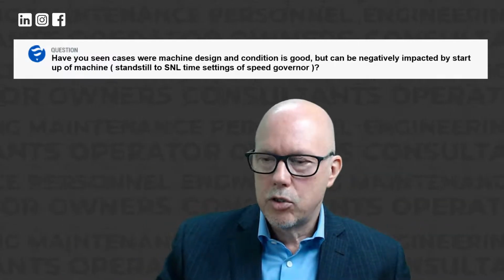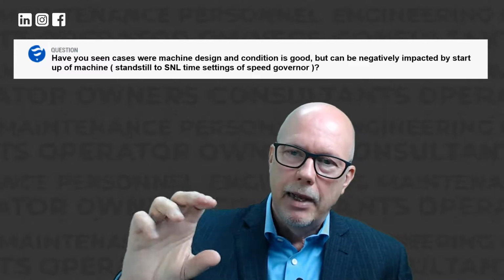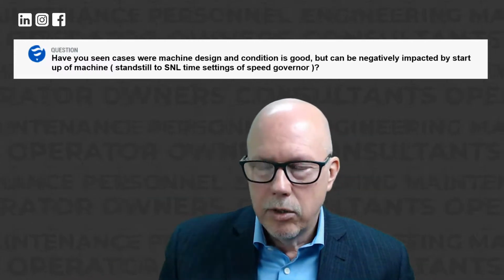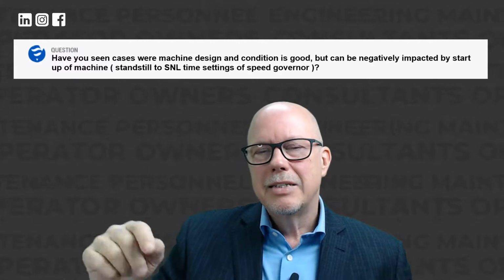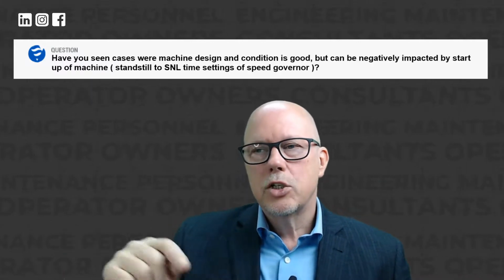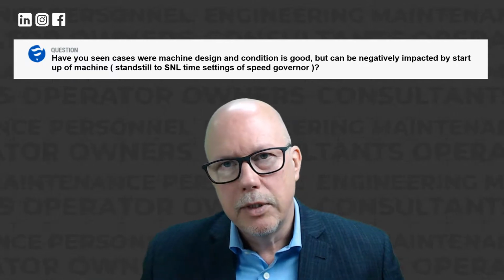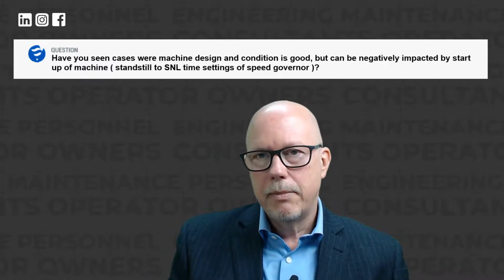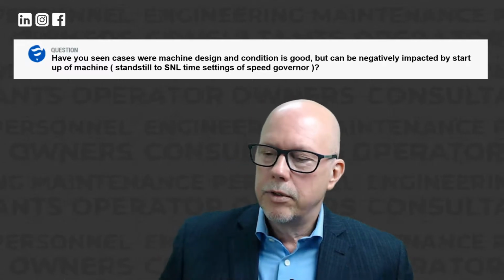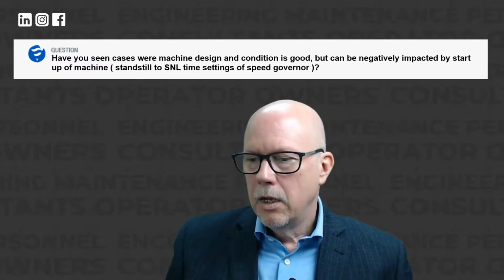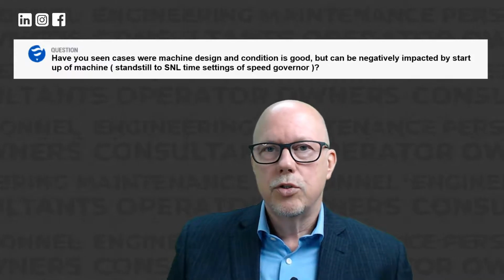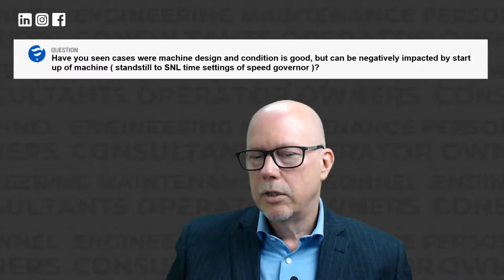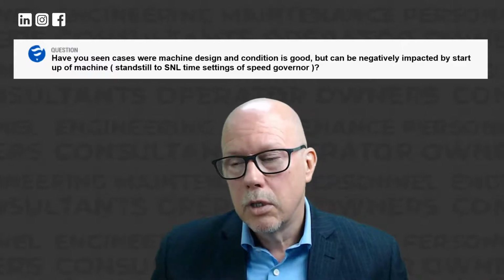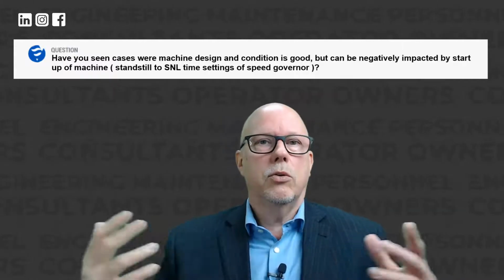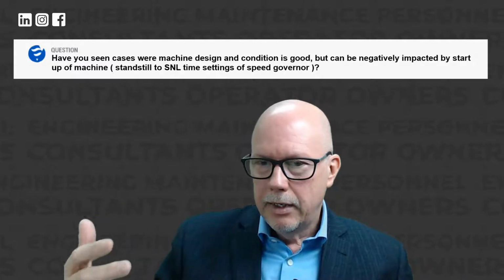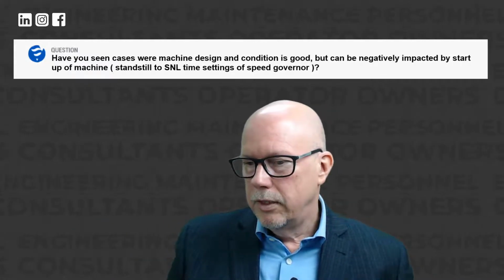To make a long story short, yes, the rim did go back to its original shape, but nobody had noticed that it did so at 78 RPM, which is actually less than the operating speed of the unit. It should have gone back to its original shape at 99 RPM. When I showed this to the commissioning engineer, he quickly saw this was a huge issue, because it meant the rotor rim could become loose during normal operation, which would be a total disaster.